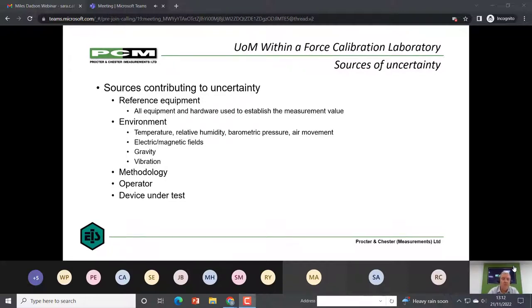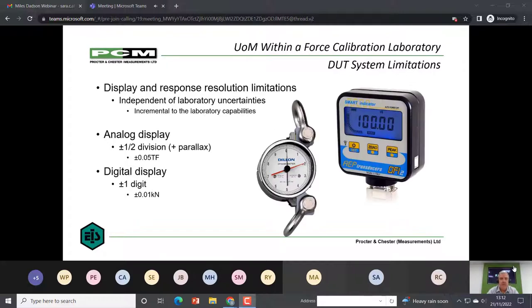So if we go into the device under test, the operation of a device under test is totally independent of the laboratory's capabilities itself. So here we've put up two examples. We have an analog force gauge on the left-hand side and a digital force gauge on the right-hand side. With the analog, first of all, the best that you could probably achieve, depending on the size of the scale, is half a division. Plus, you've also got issues with parallax, what angle you're observing that at.